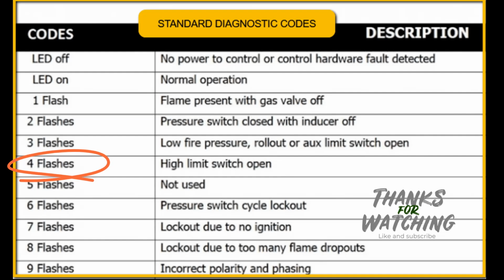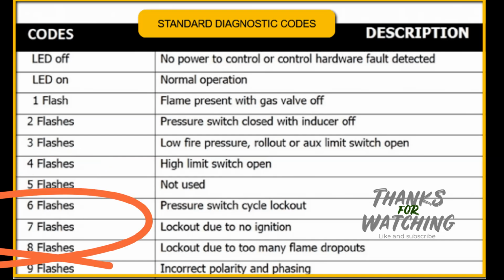If you are competent and have the right tools, check the gas pressure is not too high. See our video on setting gas valves. This should only be done by a professional. If the furnace shows a lockout code, they are generally resettable by turning off power and restarting the furnace. When you have done that, monitor the furnace to see if it is functioning correctly. If not, stay close, as it will typically show an error code before a generic lockout code.